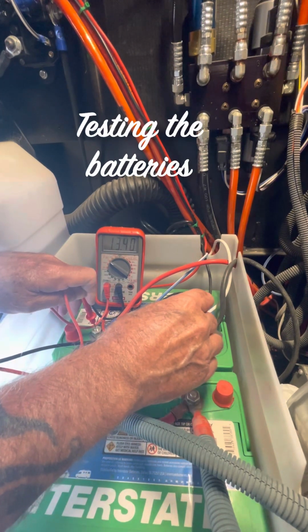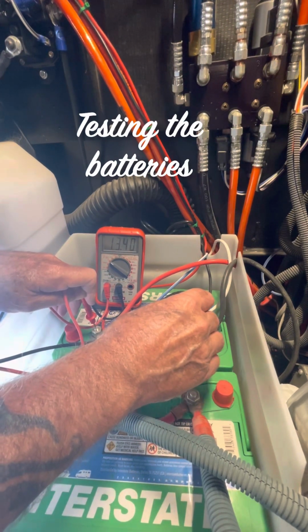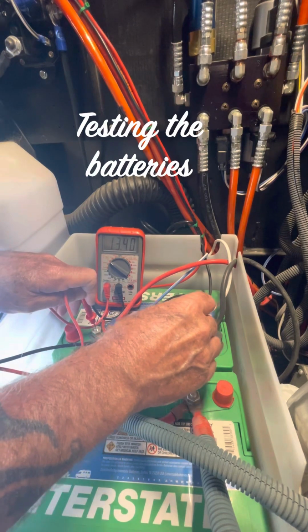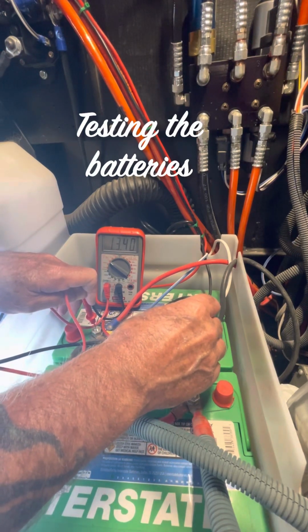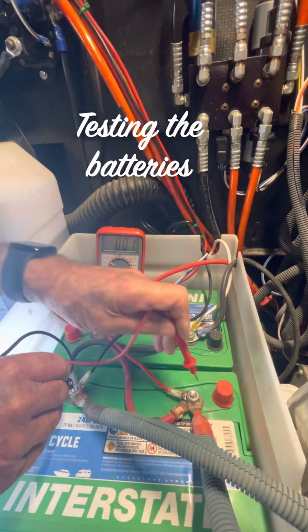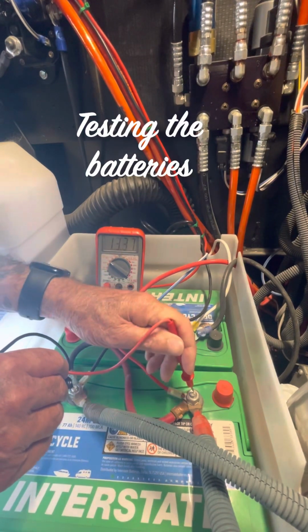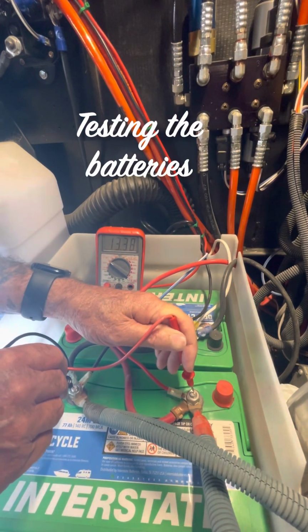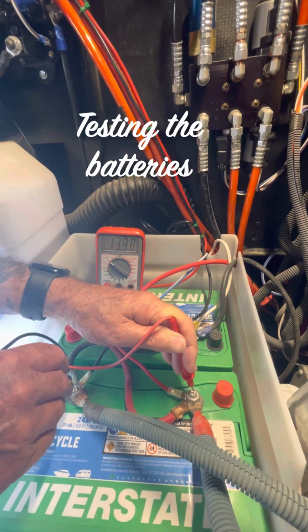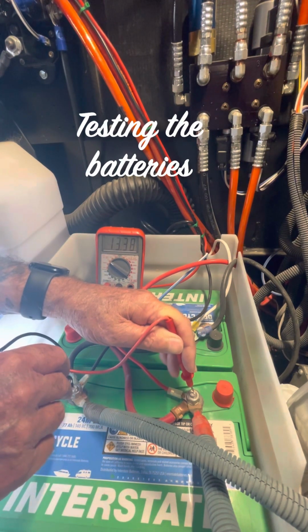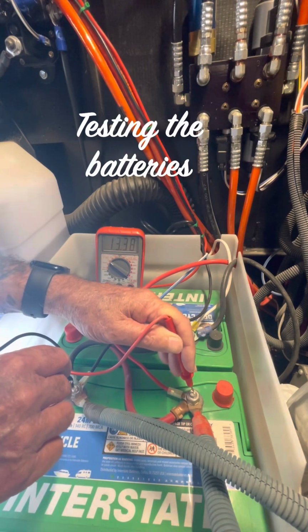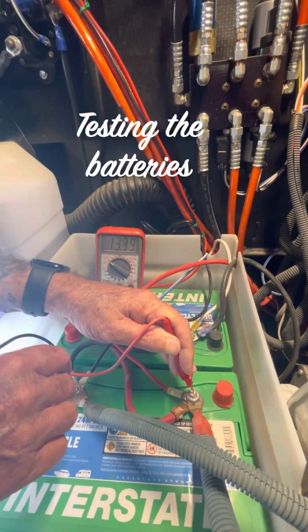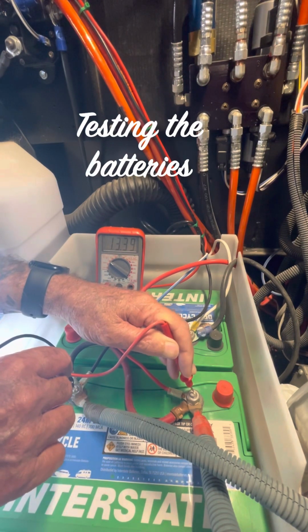So you can go ahead and troubleshoot specifically the refrigerator. If your voltage happens to be below 13 volts, then you know that your charger is not working, that you have a problem actually with the batteries or the battery system. Remember, troubleshooting low voltage is the same procedure as troubleshooting a total power loss, except the batteries are not completely dead.